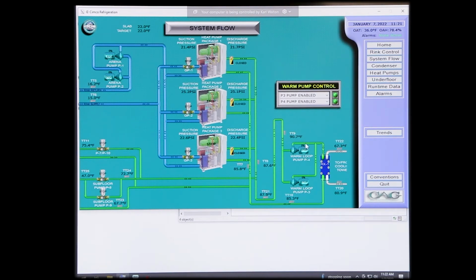You'll see here in the black the percentage of VFD run that you have. And as you watch the system run, you'll see that speed up and speed down based on glycol temperature to maintain head pressure.